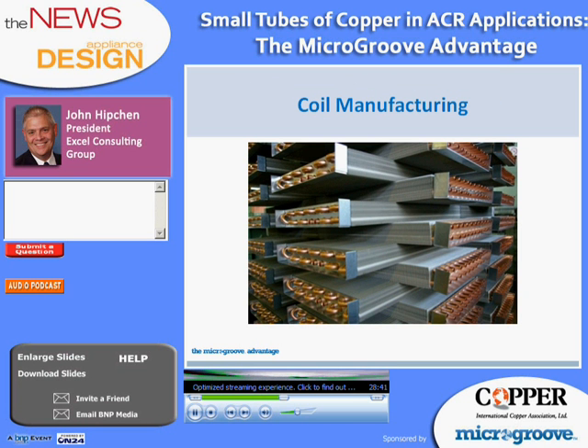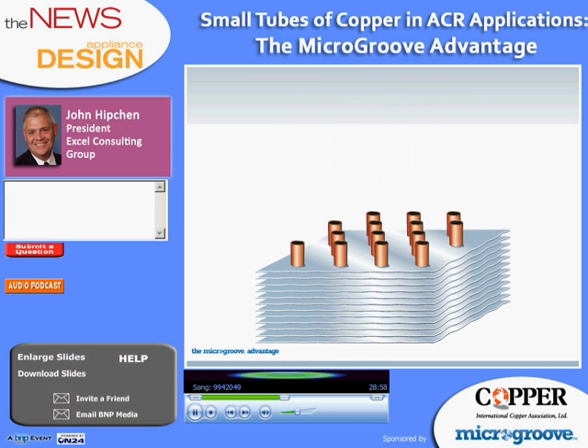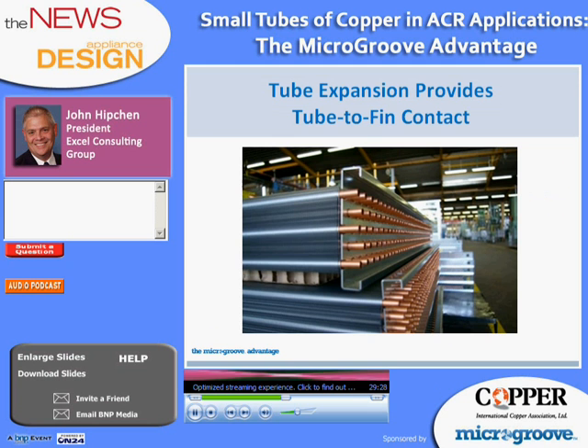Now let's talk about manufacturing coils with smaller diameter microgroove tubes. If we show this as simply as we can, a typical coil is made of tubes and a series of flat plates. The tubes are inserted through the plate fins, and plate fin spacing is maintained by the size of the collar that's formed around the holes for the tubes. Fins can be stacked prior to the placement of the tubes, and those collars around the tube holes will hold the fins at an equal spacing. The tubes are then expanded in diameter, and this binds them to the fins mechanically.